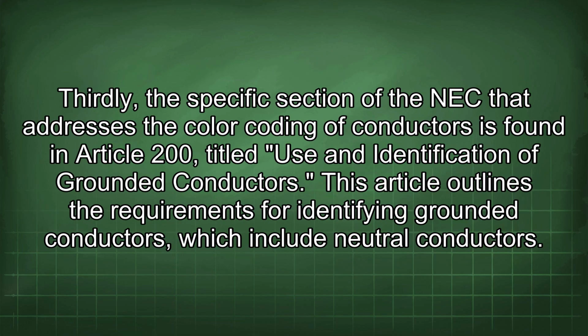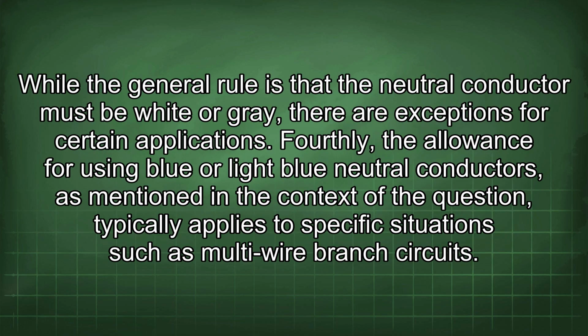Thirdly, the specific section of the NEC that addresses the color coding of conductors is found in Article 200, titled Use and Identification of Grounded Conductors. This article outlines the requirements for identifying grounded conductors, which include neutral conductors. While the general rule is that the neutral conductor must be white or gray, there are exceptions for certain applications.